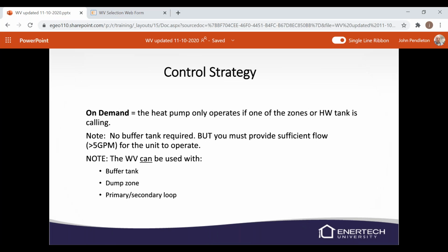We'll talk a little bit about the control strategies on the unit. So we have on demand. So the heat pump only operates if the zones or the hot water tank is calling. So no buffer tank is required, but you have to provide sufficient flow. The unit has to see 5 GPM. I think it actually is a little bit under 5 GPM, but 5 GPM is easy to remember for you guys, and that's going to keep you safe. So we've got to have that 5 GPM.